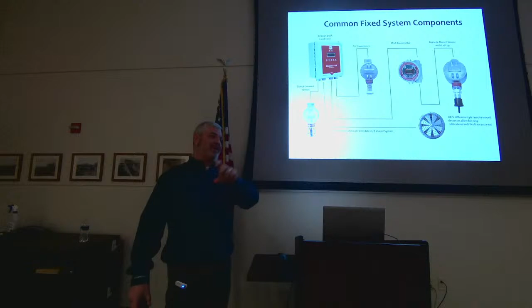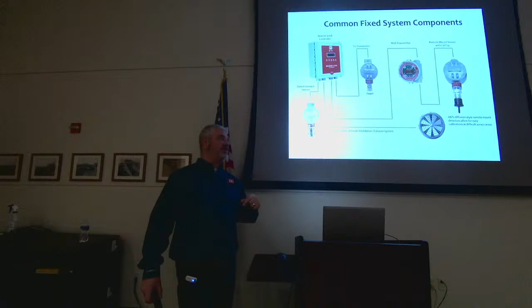That spec goes out, goes through about 15 different hands, and somehow equipment shows up at your place. So our desire is that you're always touched by a professional who knows a little bit more about gas detection than a copy and paste off of a master spec. Keep that in mind if you're doing any construction, or planning any. It may be a very small monetary piece of an overall huge project, but it's one you have to pay attention to, and it's a maintenance item. It's not a silver bullet. You do have to calibrate these things, and they are designed to keep your guys safe. So put a little extra effort into it when you're looking at it. It'll make a great difference.